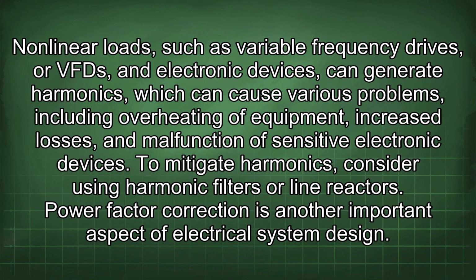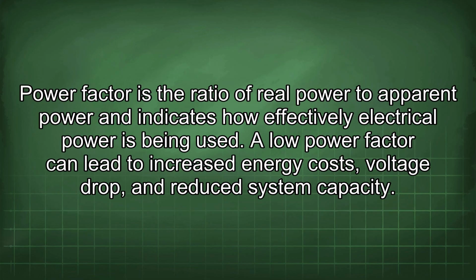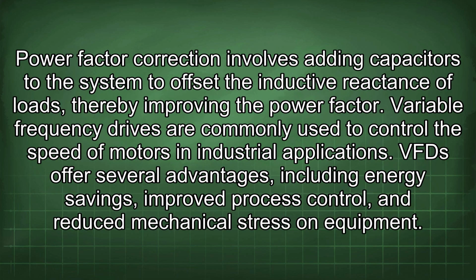Power factor correction is another important aspect of electrical system design. Power factor is the ratio of real power to apparent power and indicates how effectively electrical power is being used. A low power factor can lead to increased energy costs, voltage drop, and reduced system capacity. Power factor correction involves adding capacitors to the system to offset the inductive reactance of loads, thereby improving the power factor.